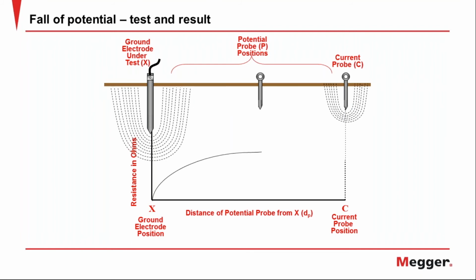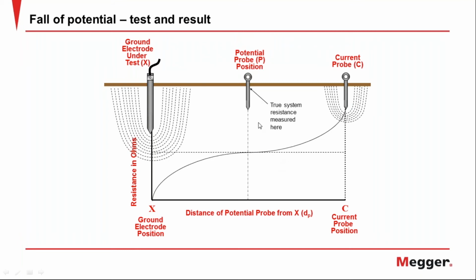You're taking a series of readings and plotting them just like we see here, and you look for this graph at the end. It's the fall of potential graph. Note here, we say usually 62%. So if this current probe was out at 100 feet, then your best reading is probably going to be at 62 feet.